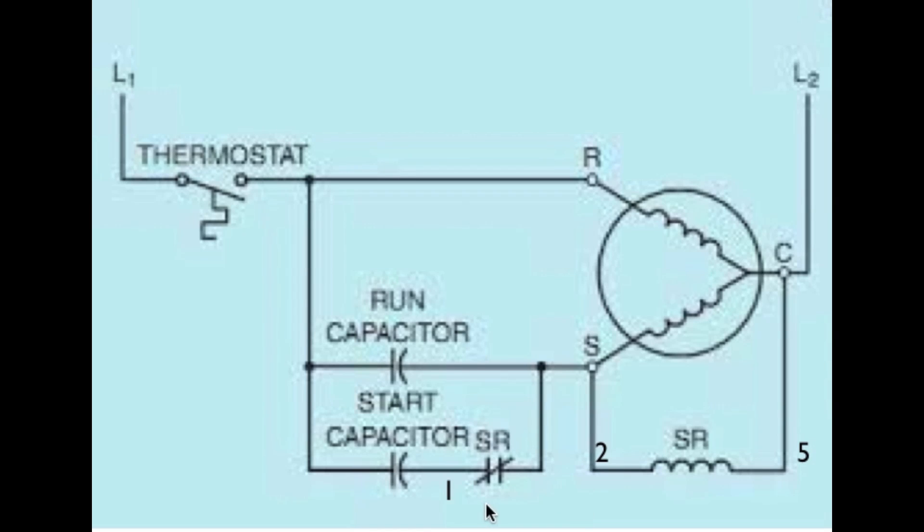So to recap everything here: terminal 5 on the relay goes to common, terminal 2 goes to start, and terminal 1 goes to the start cap.